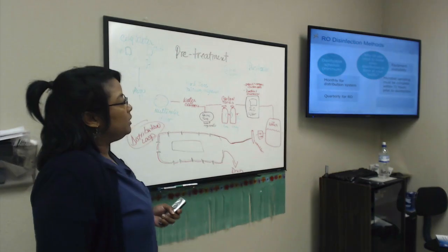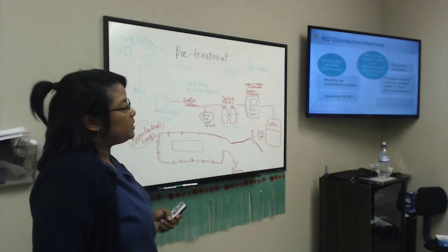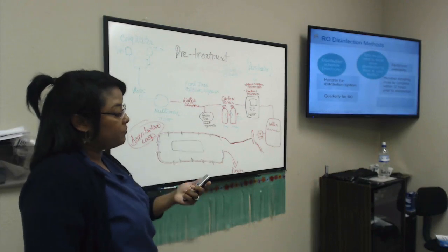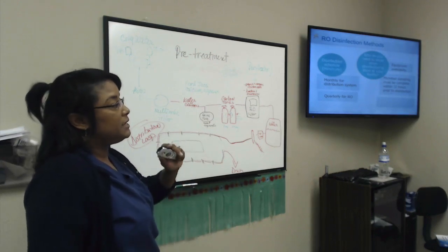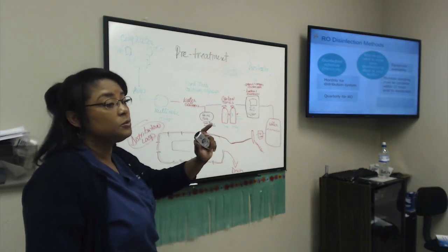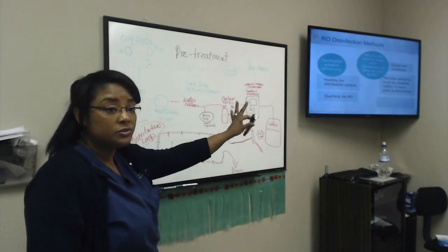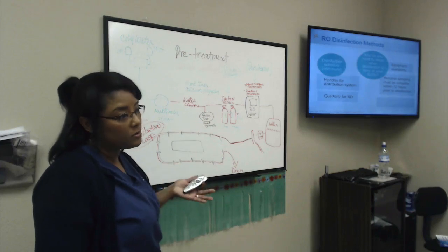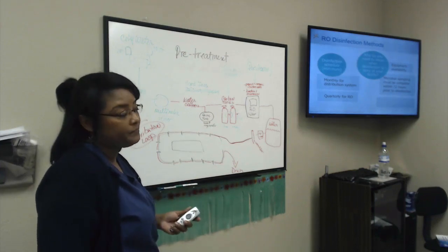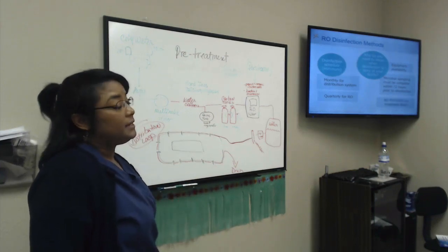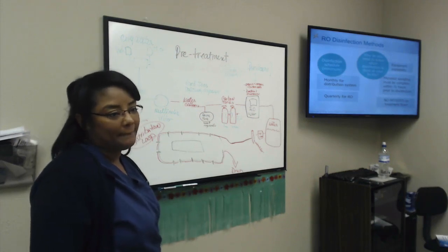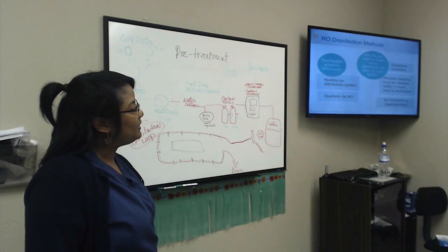So the biomed takes the microbial sampling, which must be completed within 72 hours before the disinfection, and 72 hours because usually when we send cultures in, we have to give them 72 hours to have a final result to see if something grew. And then, of course, we cannot have any patients on the treatment floor. Okay?